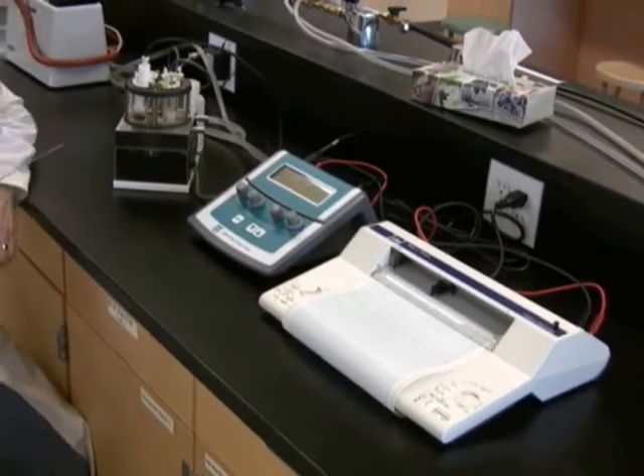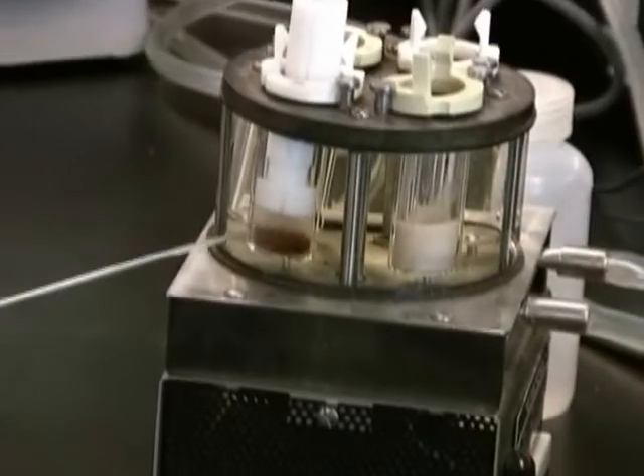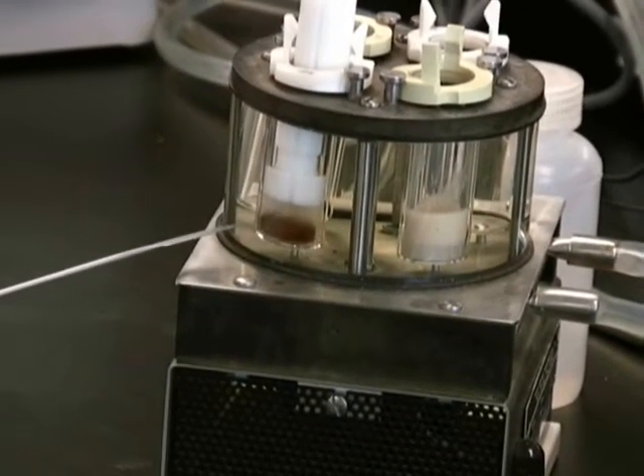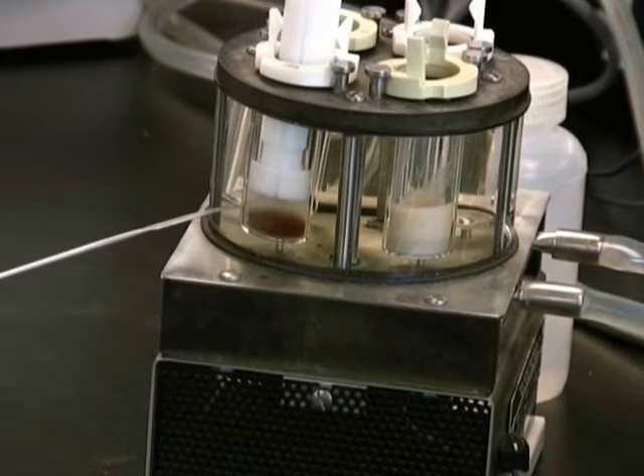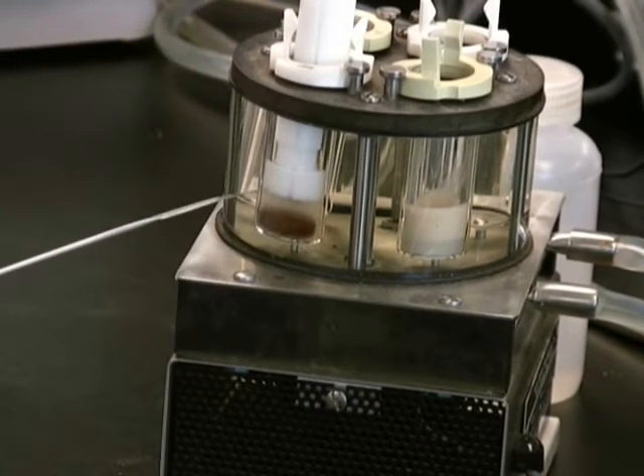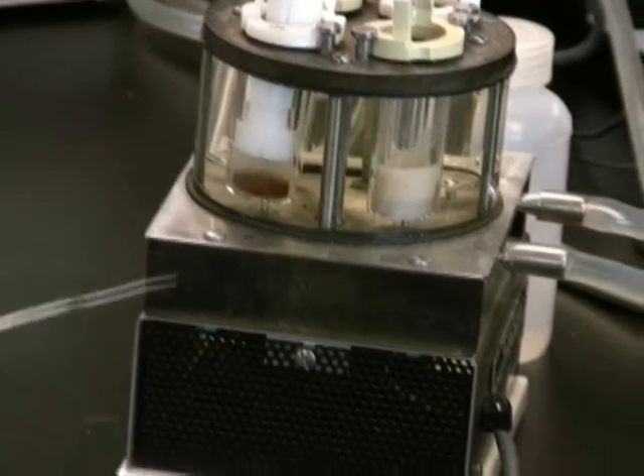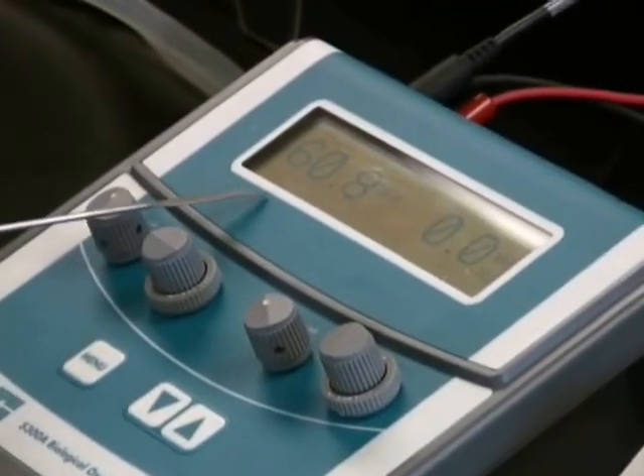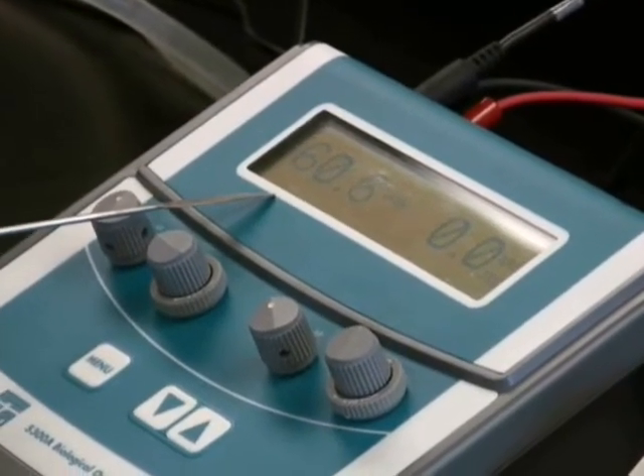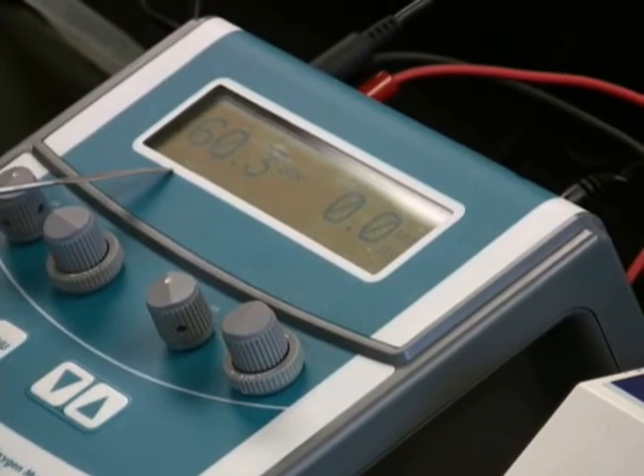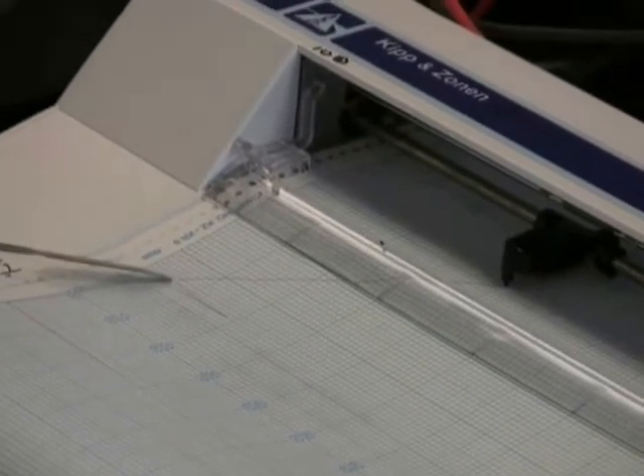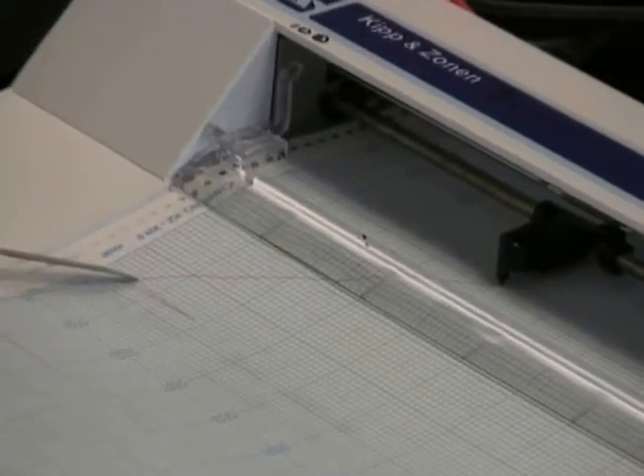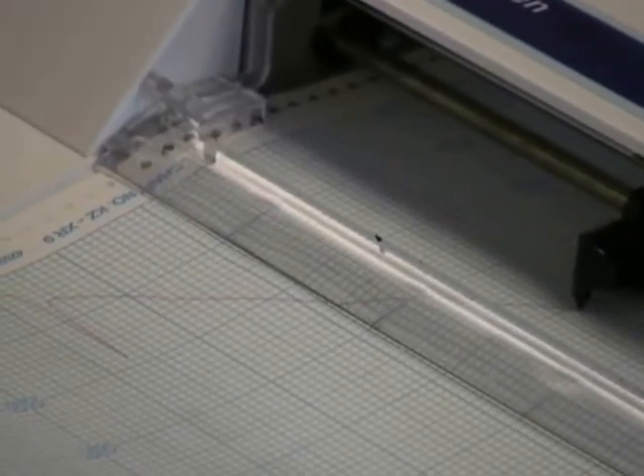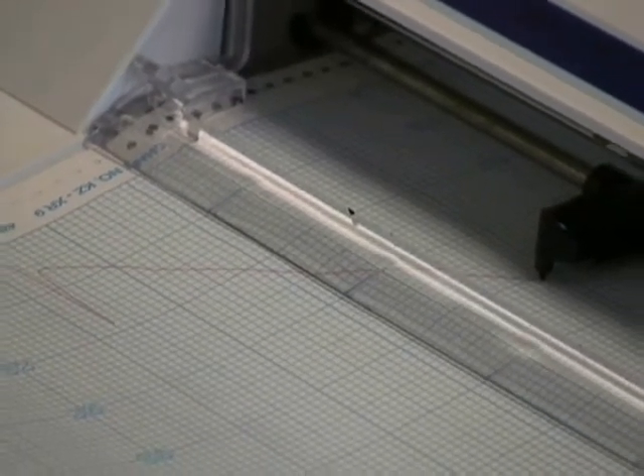Okay, so now the yeast has been added. So what's going to happen is the yeast will consume the oxygen that's in your buffer, and this will reduce the amount of oxygen available to support the gradient that we call our 100% signal. Now if we glance at the amplifier, we'll see we've gone from 100% to about 60%, indicating that 40% of the oxygen has been consumed. And on the tracing on the recorder over here, we've been tracing this for a couple of minutes now. We're observing a slope. We have a graph that is time on the x-axis versus oxygen on y. So we have a slope that is the disappearance of oxygen with time.